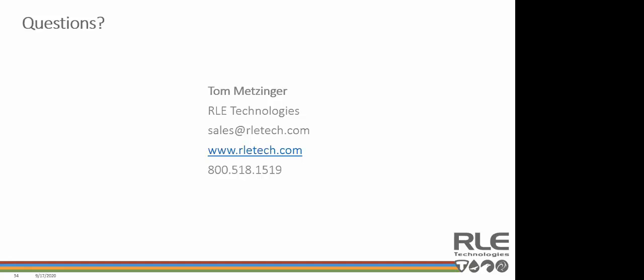Thank you, guys. Next question also looks at monitoring. What are the common applications for the RFM panel? I would say the one we see most is to measure differential pressure between the floor plenum under your raised floor and the open space in the data center. It's pretty convenient. You can just pop it in. It's wireless, so once you have the sensor mounted in the floor panel, it's very easy to move that floor panel from location to location.